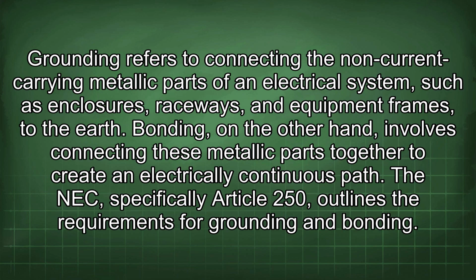Grounding refers to connecting the non-current carrying metallic parts of an electrical system, such as enclosures, raceways, and equipment frames, to the earth. Bonding, on the other hand, involves connecting these metallic parts together to create an electrically continuous path. The NEC, specifically Article 250, outlines the requirements for grounding and bonding.